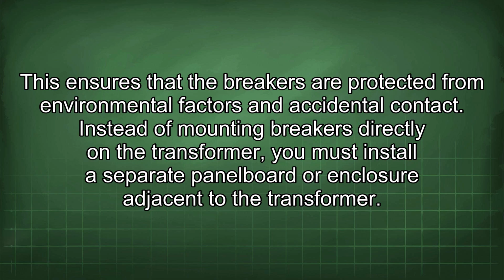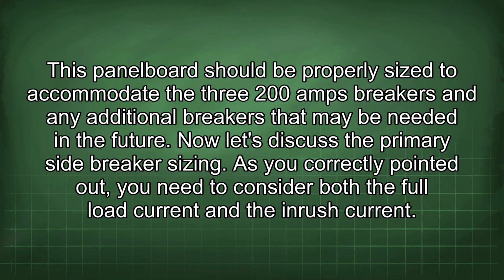Instead of mounting breakers directly on the transformer, you must install a separate panel board or enclosure adjacent to the transformer. This panel board should be properly sized to accommodate the 3 200 amp breakers and any additional breakers that may be needed in the future. Now let's discuss the primary side breaker sizing. As you correctly pointed out, you need to consider both the full load current and the inrush current.